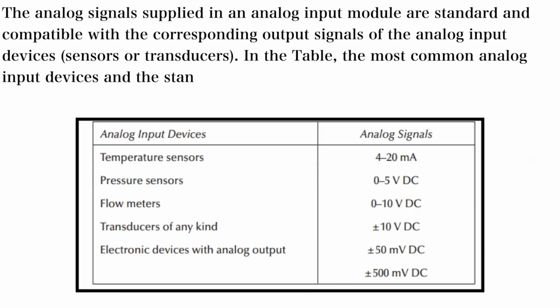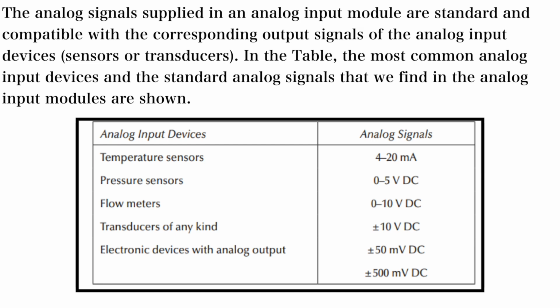These analog signals supplied to an analog input module are standard and are compatible with the corresponding output signals of the analog input devices, which are mainly sensors or transducers. In the table, you can see the most common analog input devices and the standard analog signals that we can find in analog input modules. Here the common analog input devices are listed with their analog signal range.